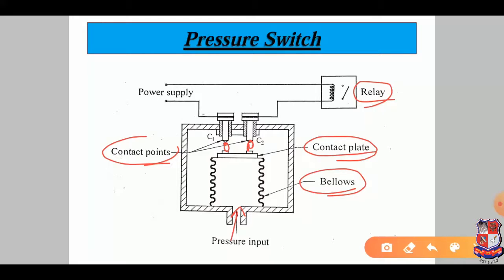One use of pressure switch is to protect against overheating of computer panel. In computer panel, blowers are used for cooling the computer circuit and panel components. Whenever the blower fails due to any reason, a pressure switch is operated which cuts off the power supply to main panel. Hence, computer panel components are protected against overheating. Another use of pressure switch is to limit the steam pressure in steam power plant. The pressure switch is used to operate a safety valve which releases the steam when the pressure exceeds the predefined value.